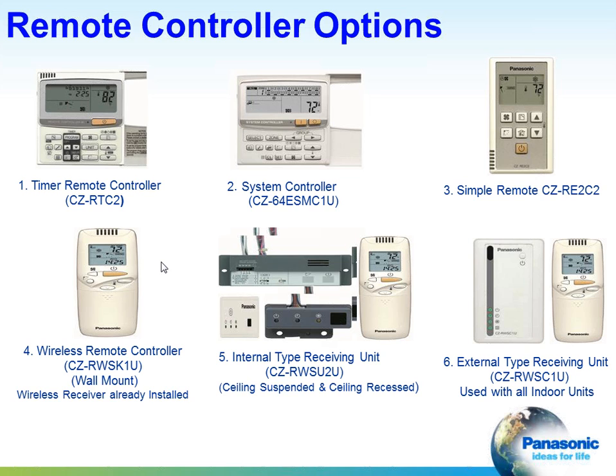And then we have the wireless ones. Some of them are 2 parts. When you go from the provided wired controller for the cassettes and for the ceiling suspended, if you want to install a wireless, you have to mount a receiver inside those units, and then you have a controller that mounts on the wall. That would be number 5. One of those receivers, the top one is meant for, I believe, the ceiling suspended, and the bottom one is meant for the ceiling cassette.